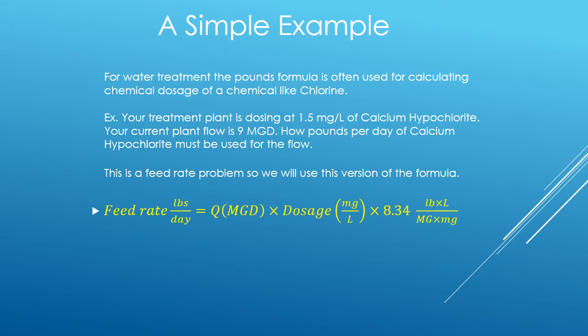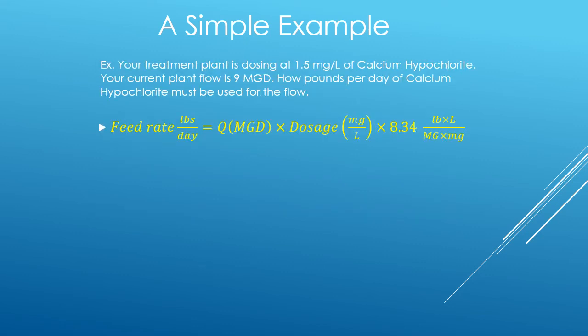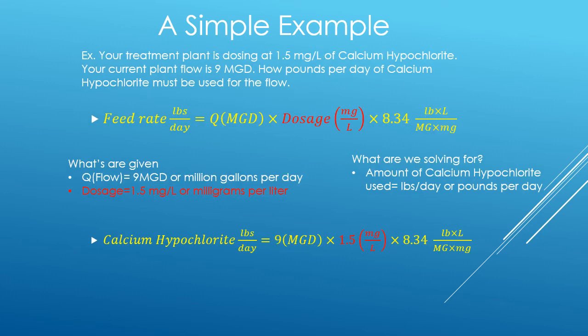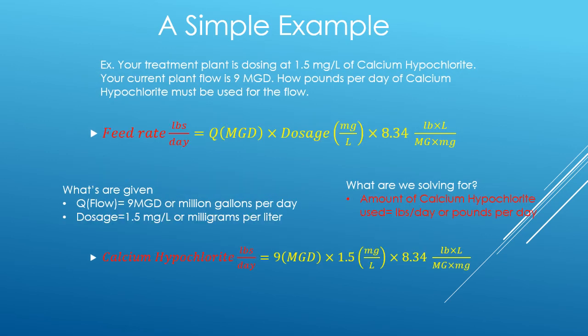After reading the problem, we know this is going to be a feed rate problem, so we select the feed rate equation. Let's see what we're given. First, we're given our flow, which is 9 MGD or 9 million gallons per day. We're given our dosage, which is 1.5 milligrams per liter. And we're trying to solve for our feed rate, which in this case is calcium hypochlorite in pounds per day.